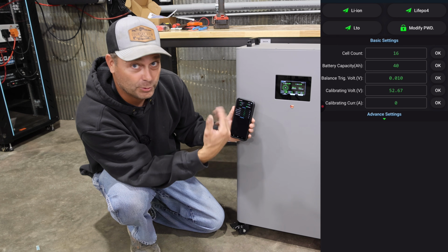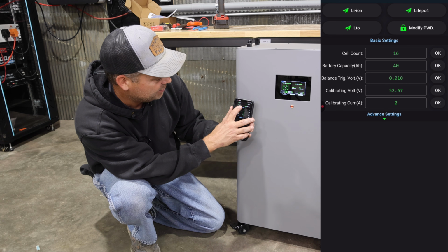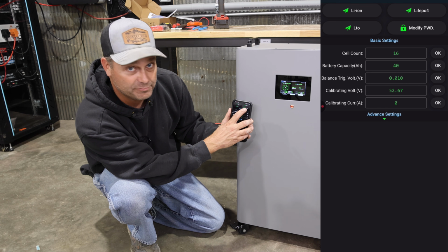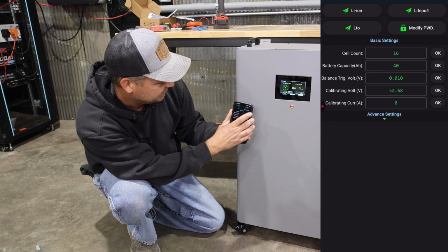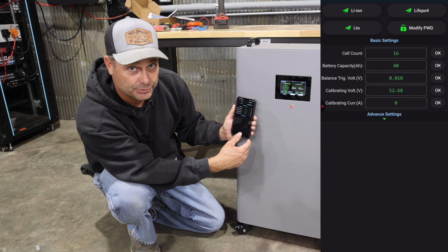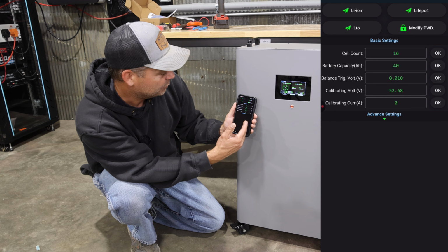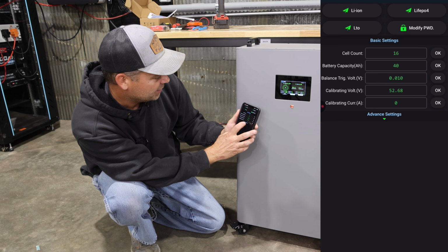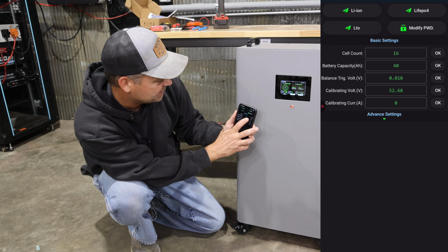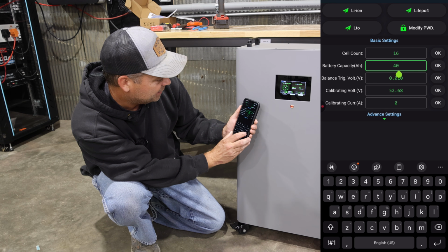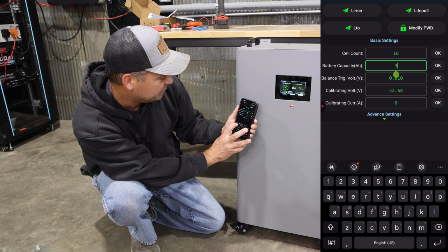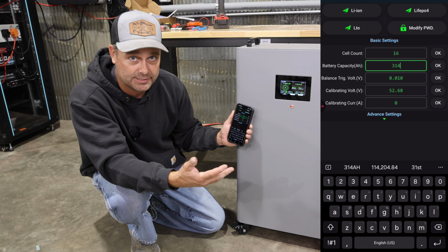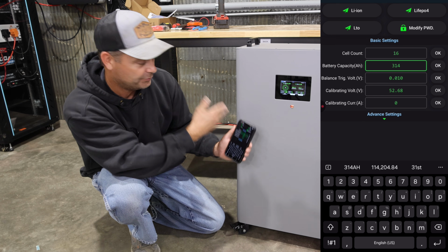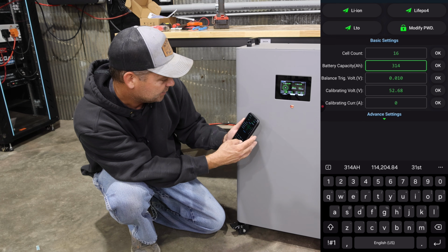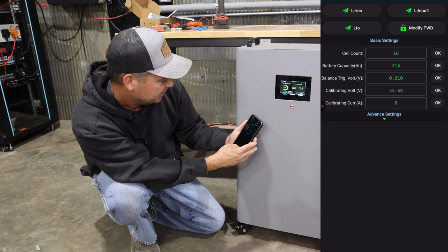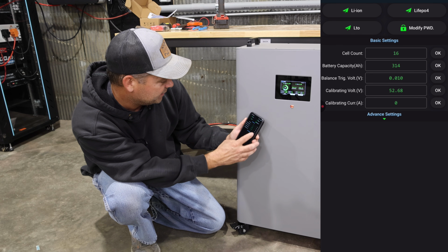Now one way to program this quickly, on this screen you have some presets up here. One says LiFePO4. If you click that, it will automatically do the default settings for a LiFePO4 battery. The one thing you will have to change is where it says battery capacity, it says 40, and we need to change that to 314, at least that's the size of the battery cells that we have. They're 314 amp hours, so we'll set that. And of course there are 16 batteries.